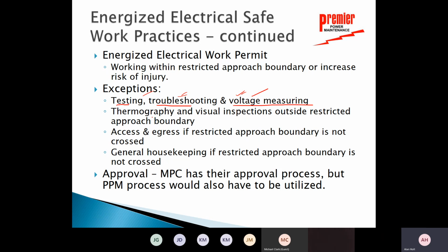Now, there are areas where I can do thermography and visual inspections. I can stand outside the restricted approach boundary and do that thermography and visual inspection. That does not require an energized work permit. So the thing I want you to understand is if you're inside the restricted approach boundary, that's key. Inside that boundary doing work.